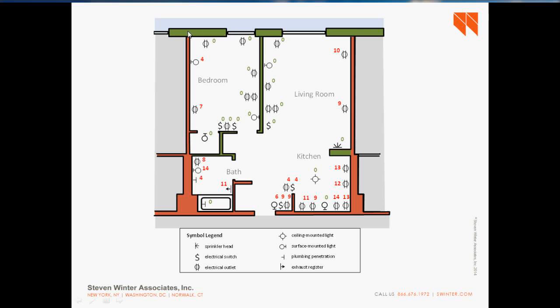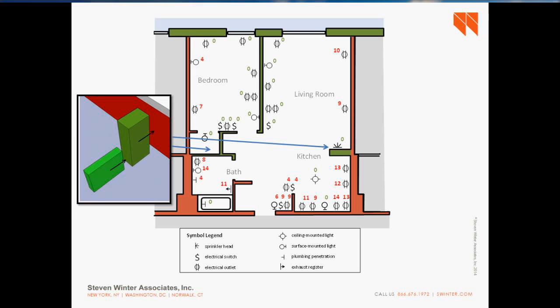One thing of note for this building is that it was an ICF building, an insulated concrete forms building. The exterior wall was poured concrete, so it's a pretty darn good air barrier. As a result, the interior walls applied to that airtight exterior wall were completely sealed even before the aerosol, so that was interesting to verify. This is before the aerosol, and then after the aerosol. Oh, I forgot that they also used the layered drywall approach, from that picture from before. The walls that they used that approach on had 0 leakage to begin with. So again, effective drywall layering will do a lot for effective air sealing.